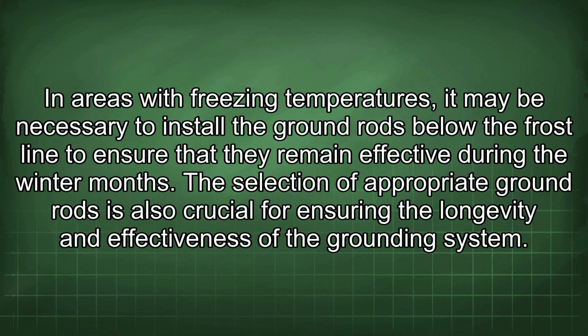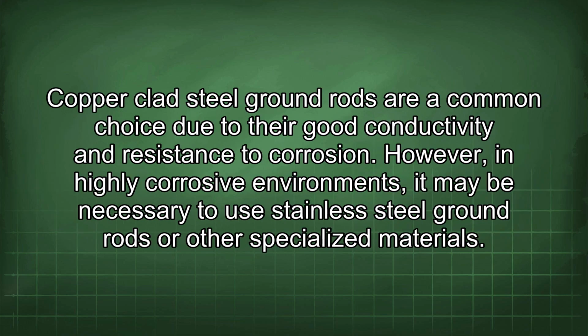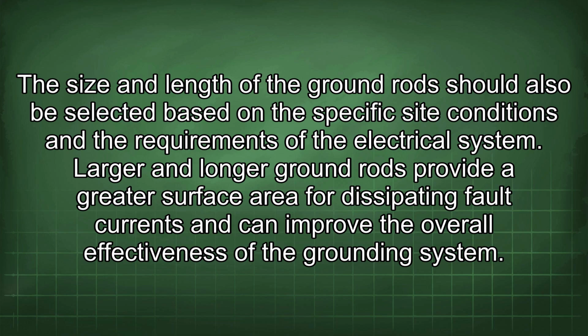The selection of appropriate ground rods is also crucial for ensuring the longevity and effectiveness of the grounding system. Copper-clad steel ground rods are a common choice due to their good conductivity and resistance to corrosion. However, in highly corrosive environments, it may be necessary to use stainless steel ground rods or other specialized materials. The size and length of the ground rods should also be selected based on the specific site conditions and the requirements of the electrical system. Larger and longer ground rods provide a greater surface area for dissipating fault currents and can improve the overall effectiveness of the grounding system.